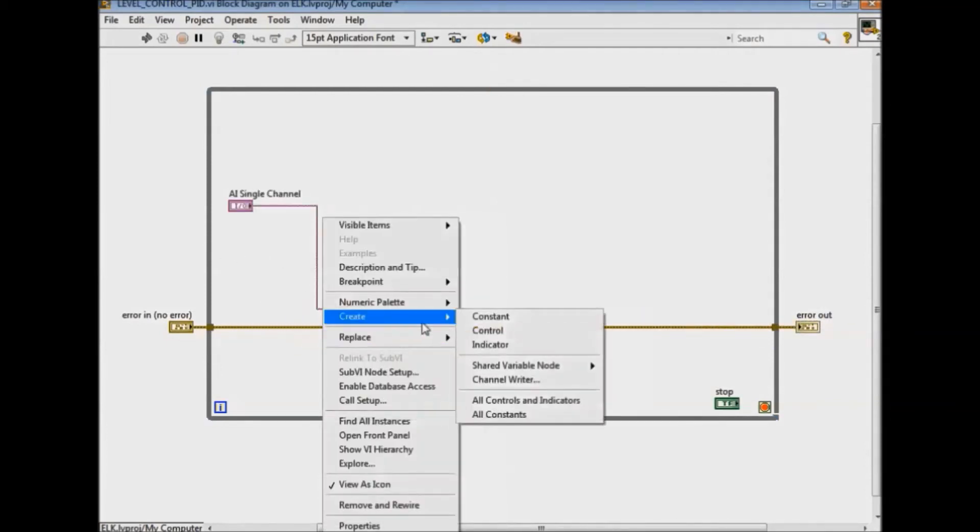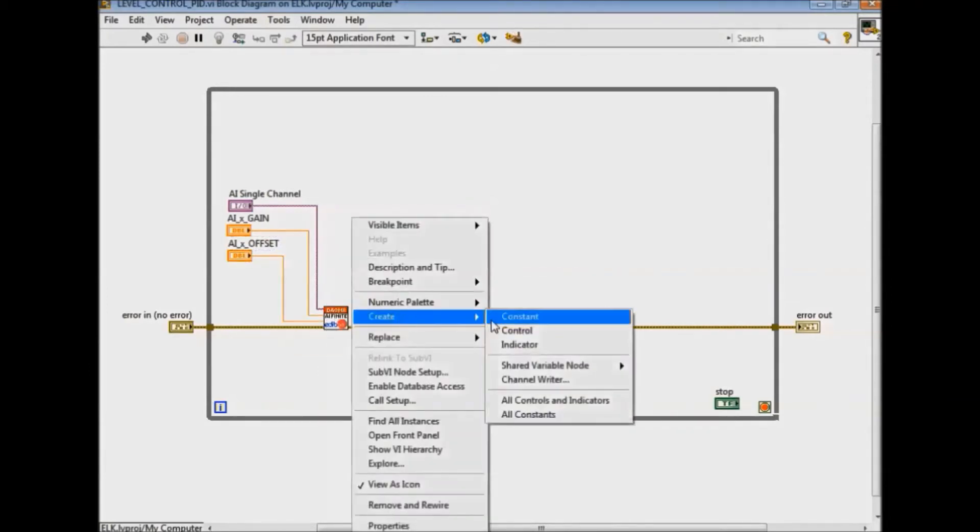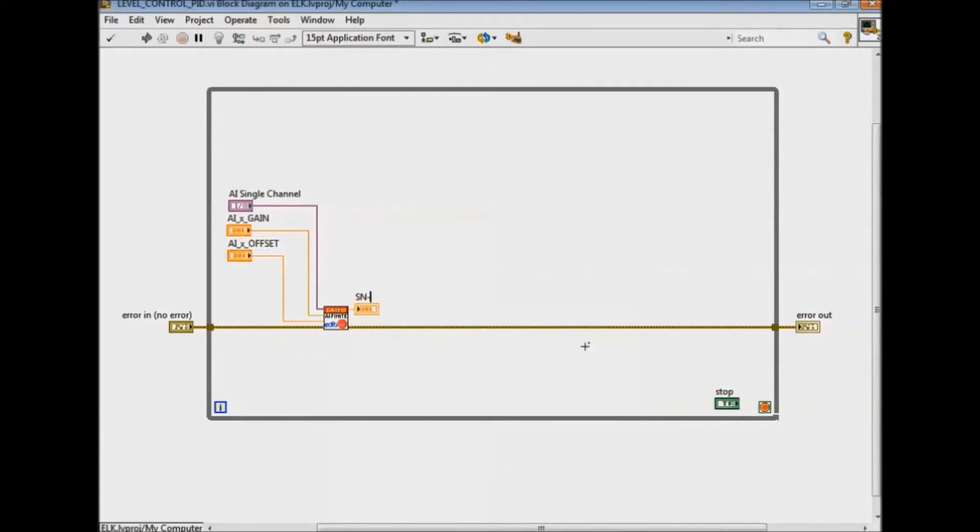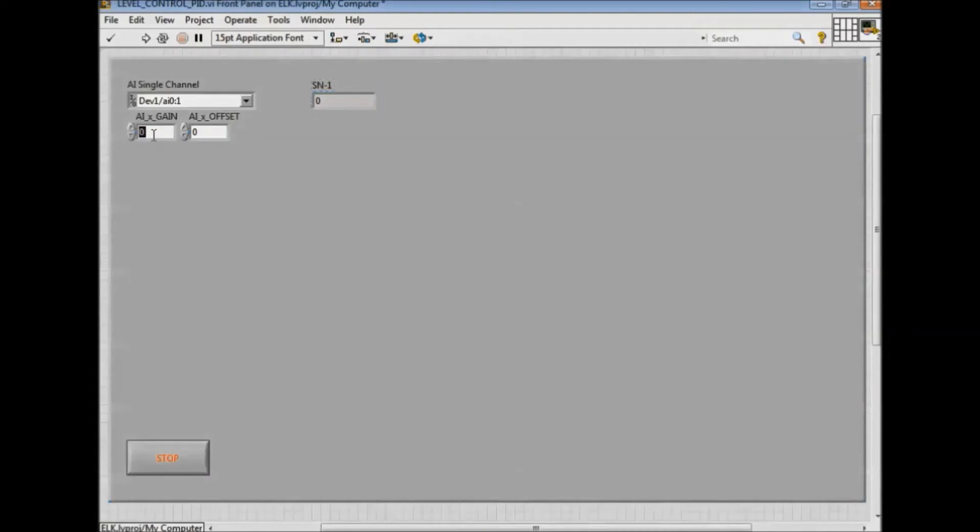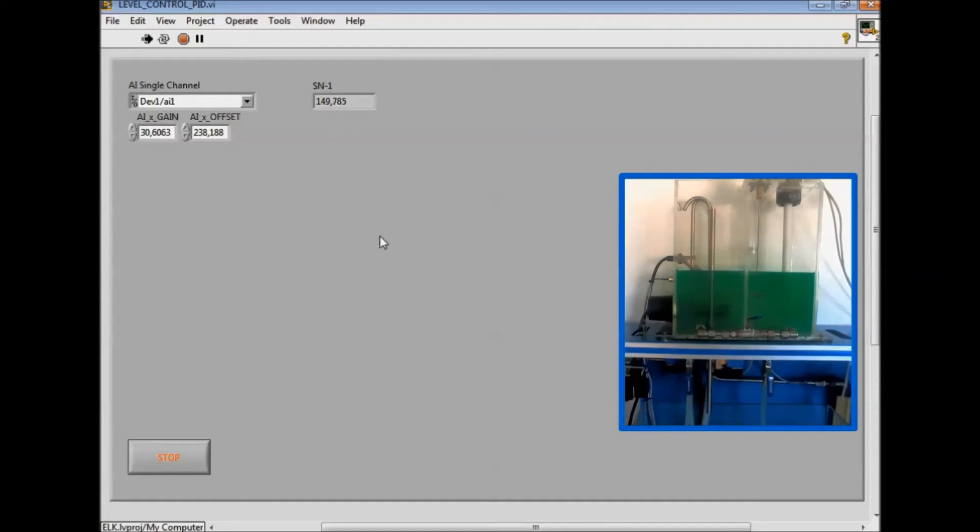For proper signal acquisition we must apply gain and offset values with the purpose of scaling the signal to the desired unit of measurement, as well as configure the physical signal to be acquired. To check it we're going to open the valves manually and observe how the water level decreases.